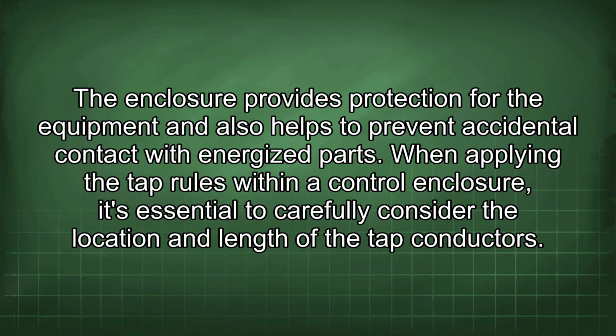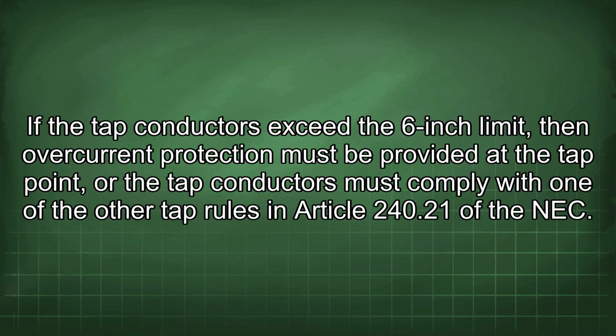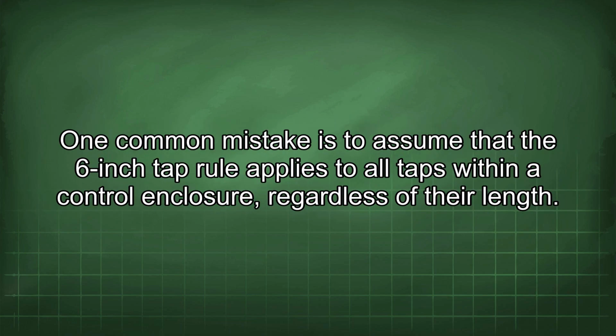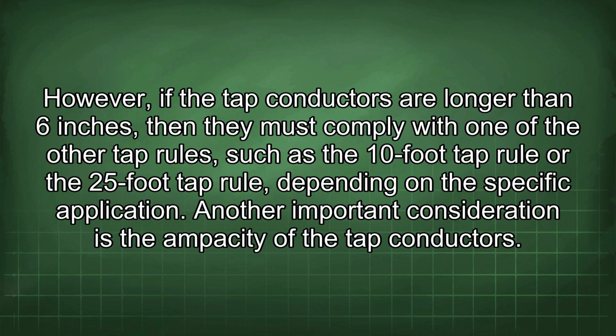When applying the tap rules within a control enclosure, it's essential to carefully consider the location and length of the tap conductors. If the tap conductors exceed the 6-inch limit, then overcurrent protection must be provided at the tap point, or the tap conductors must comply with one of the other tap rules in Article 240.21 of the NEC. One common mistake is to assume that the 6-inch tap rule applies to all taps within a control enclosure, regardless of their length. However, if the tap conductors are longer than 6 inches, then they must comply with one of the other tap rules, such as the 10-foot tap rule or the 25-foot tap rule, depending on the specific application.